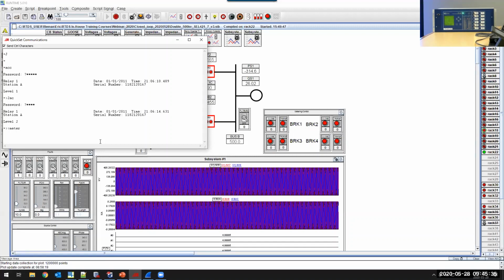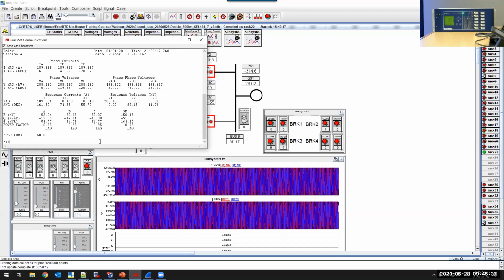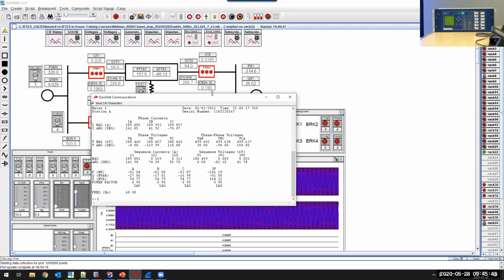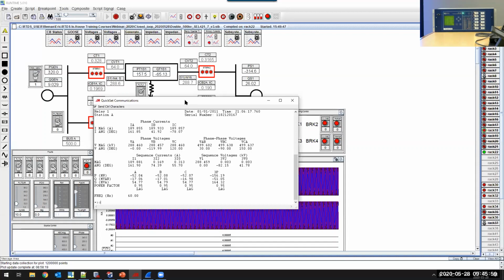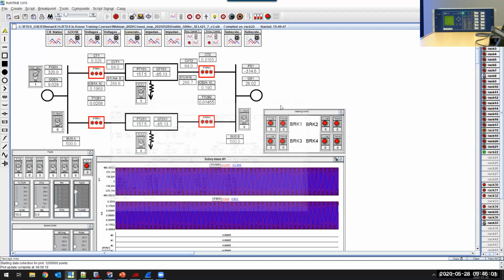So let's just meter, so we get a capture from the relay, okay? So we can compare this with the runtime values that we're sending. 189, that's the current, and 288.7. Now, depending on the CT/PT ratios, how accurately you enter the ratios, this may vary a little bit. All right, so now we are ready to apply some faults.